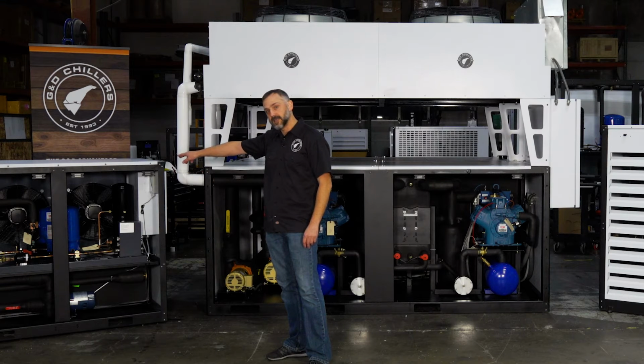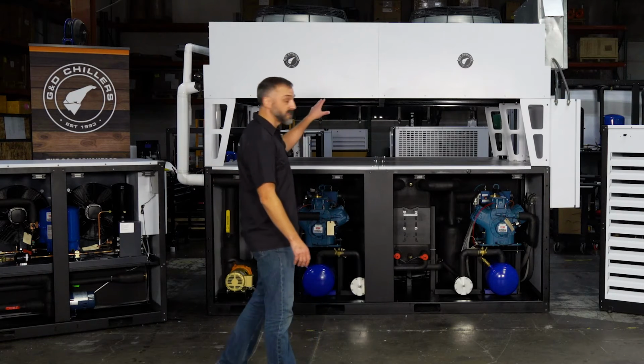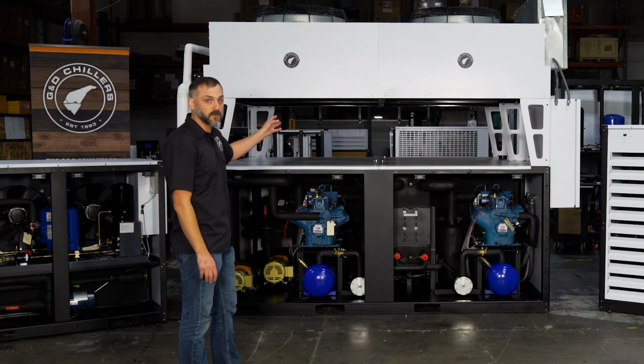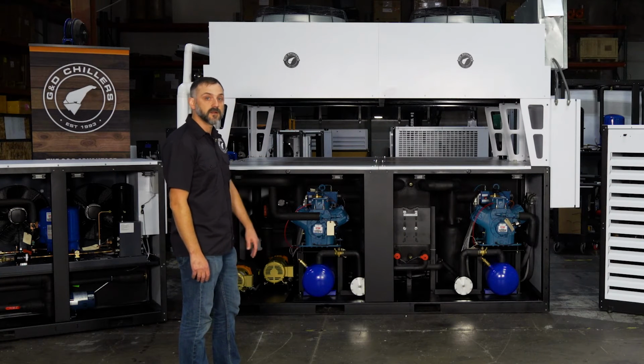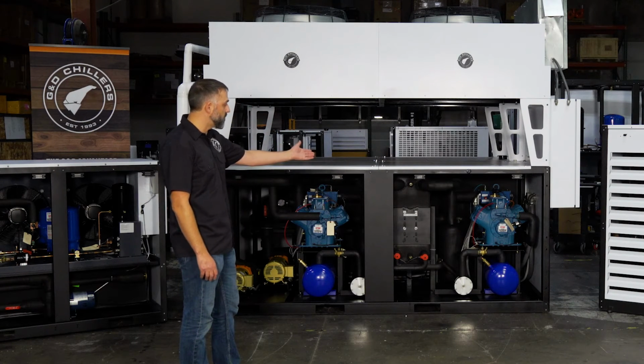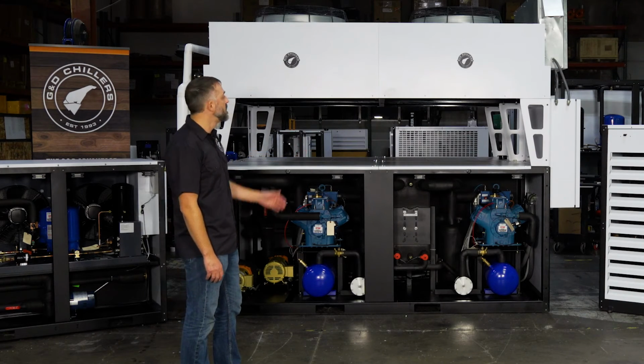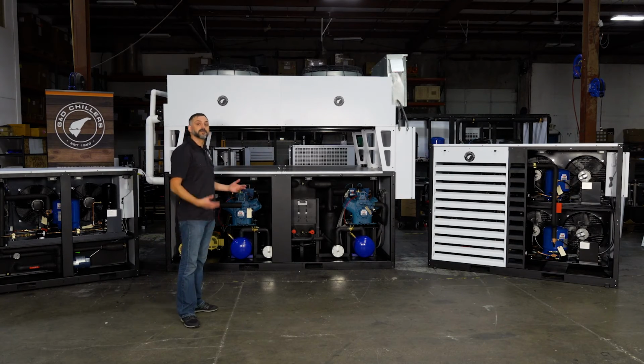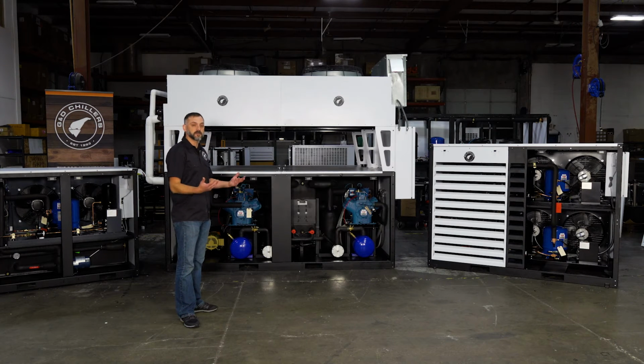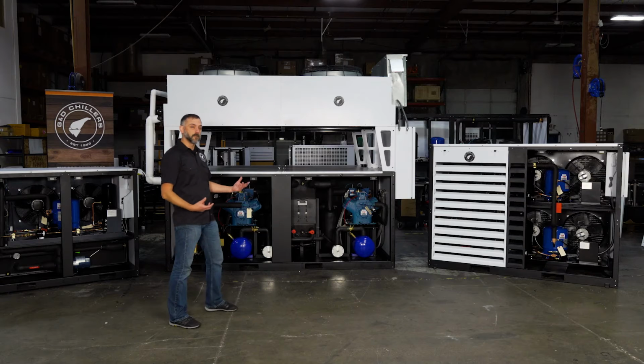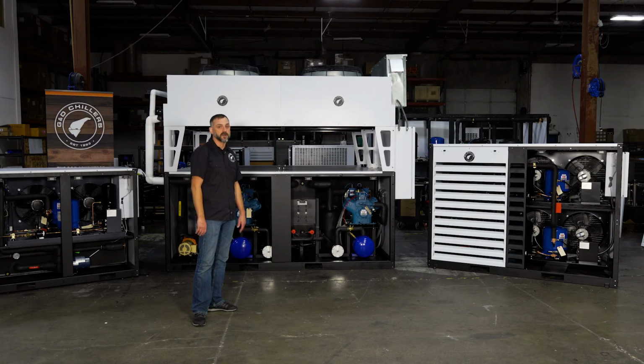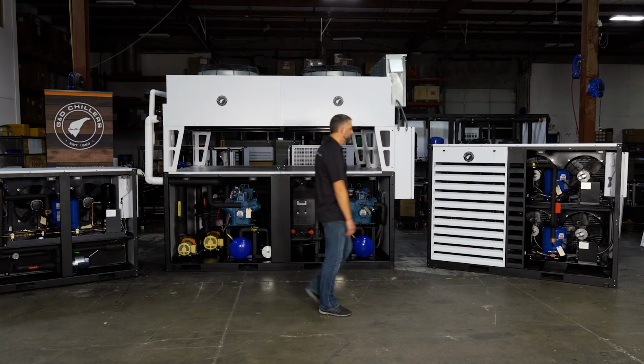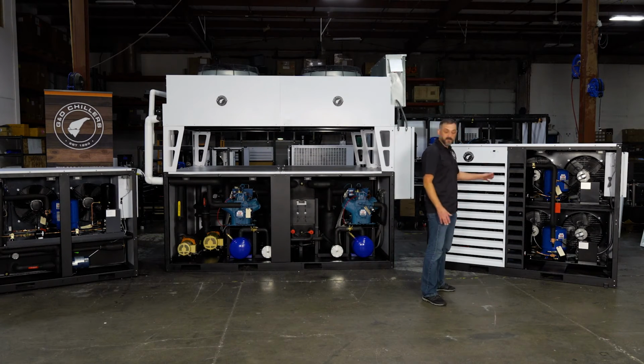You do have some redundancy on the condenser fans. They will cycle on and off as needed. To the next level on this though, there's actually 4 fans on our 70 horsepower chiller, and they will do the same. They're also variable speed motors, just like the unloading of our compressors. So this is a larger scale production brewery chiller that services the needs of somebody who's coming in with, I would venture to say, a 30 barrel brew house size, and you're going to jump right into some serious production. Or maybe it's phase 2 of a planned expansion. Maybe it's year 5 and your brewery's doing awesome and you can't make enough beer. That's your chiller.